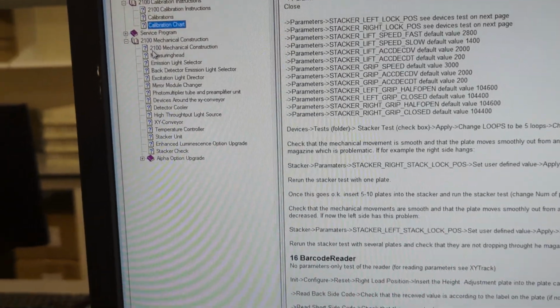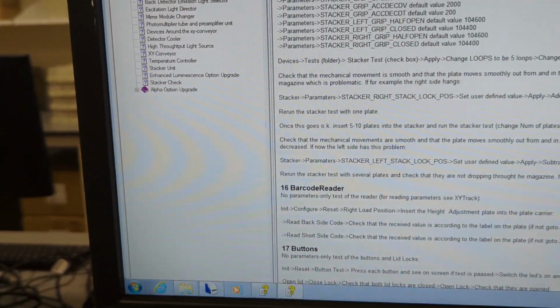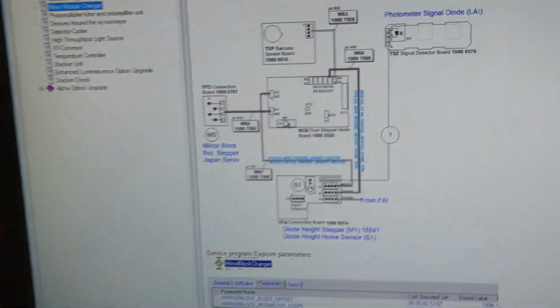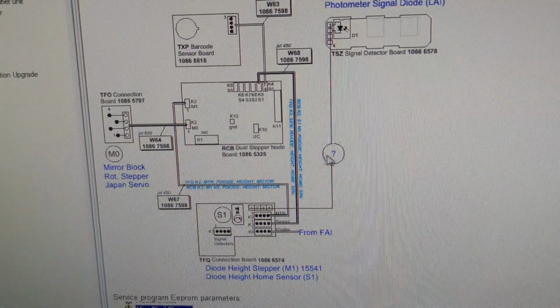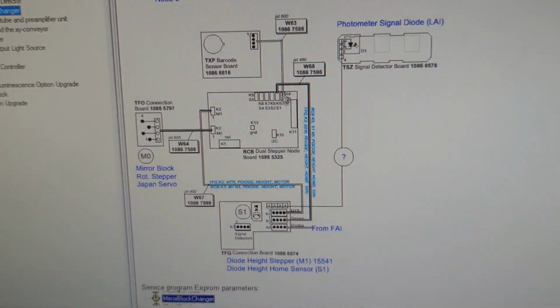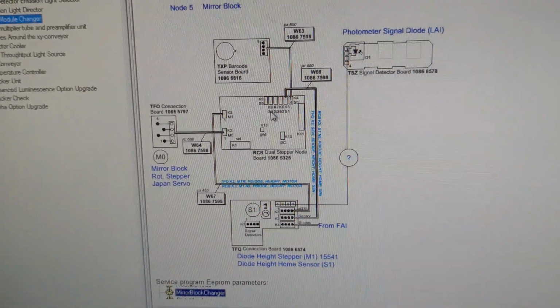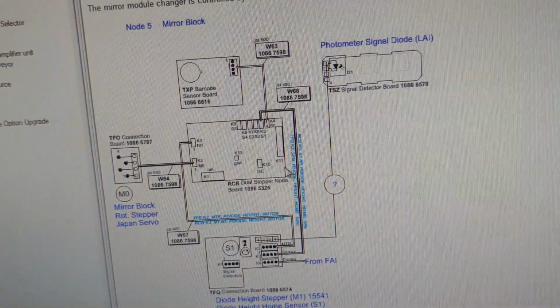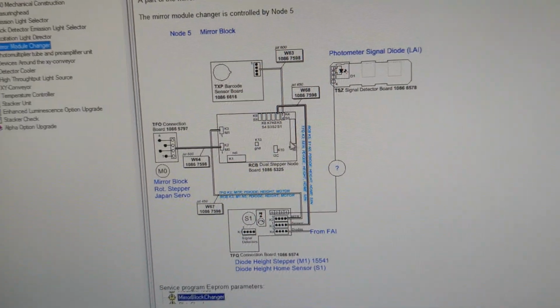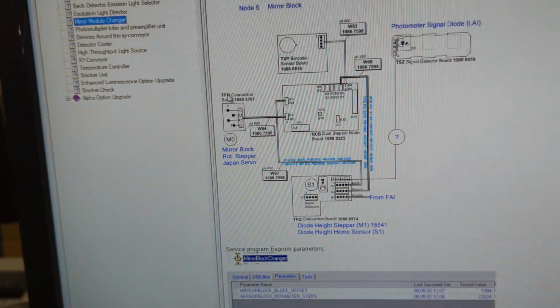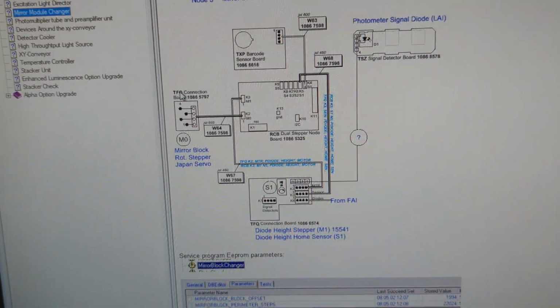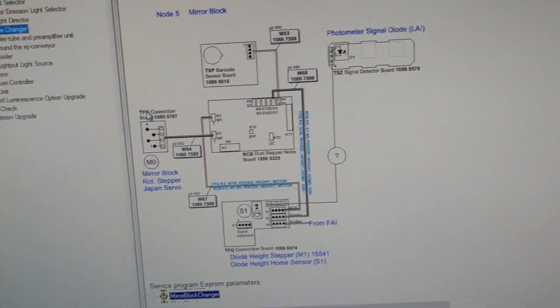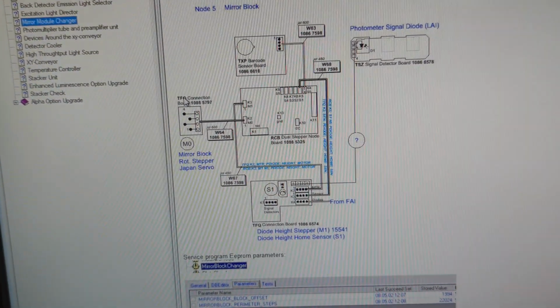Now, this help app is more specific to that older instrument here, and I can give you an example. If we look at the mirror module changer, this is the dual stepper motor board, and you can see this is not at all what this board looks like in the newer version. So it can trip you up a bit. Just be aware of that. This is going to look a lot more similar to the 2100 Envision. And for the newer models, it can still be helpful, but it's not going to be a direct reference, that's for sure.